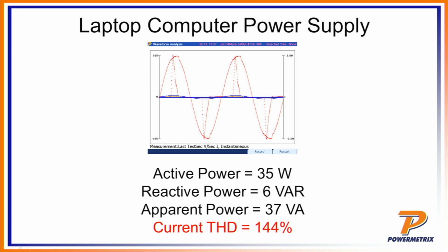And so as such, European bulbs are going to be a lot closer in terms of the power being metered to what's actually being consumed. Pass that cost along to the customer, it may cost an extra couple of cents. So from the customer's point of view, they're still getting a good deal because they're still consuming far less wattage. It's a good deal for the utility because once again, the VA being produced is very close to the watts that's being metered.